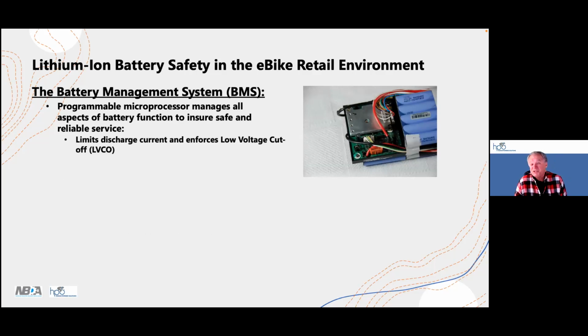One, it limits the discharge current. We talked about it before with the low power density lithium-ion batteries. Pulling too much current out of those batteries would cause a problem. The same is true for the high power density, energy density batteries. There is still a limit. And what we do with the battery management system is we program in that upper current limit. It's usually between 18 and 24 amps. In other words, the BMS will not allow you to pull more current than what it is capable of sustaining. So if you try to do that, it will limit the current output of the battery to ensure that it stays safe.